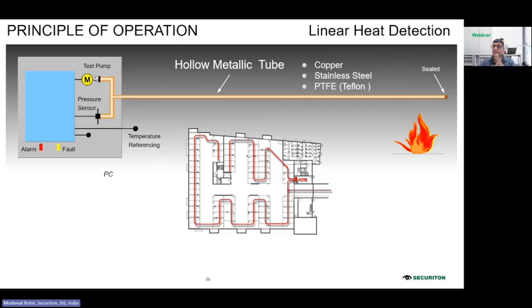ADW535 detects fire in two ways. One is the differential principle, which is rate of rise. So if the temperature is increasing rapidly because of the explosion, because of the flashover, the air expands very quickly. So the system detects this sudden pressure rise and triggers an immediate alarm. And then it also works on a maximum principle, which is fixed temperature detection.